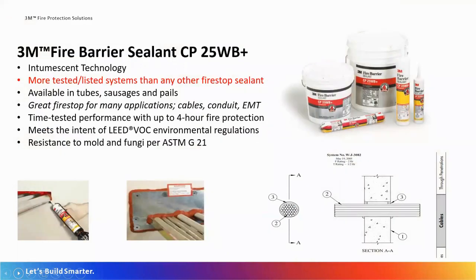The first product we're going to look at today is the workhorse of the 3M firestop line. This is our CP25WB Plus, an intumescent firestop sealant. We have more UL tested assemblies with this sealant than any other firestop sealant. It's available in tubes, sausages, and pails, and it's a great firestop product to be used with cable, conduit, and EMT. In addition, this product can be used in conjunction with a few of the other firestop products that I'm going to talk about in the next few slides. With some of our tested systems, we can provide up to 4-hour protection with the CP25WB.